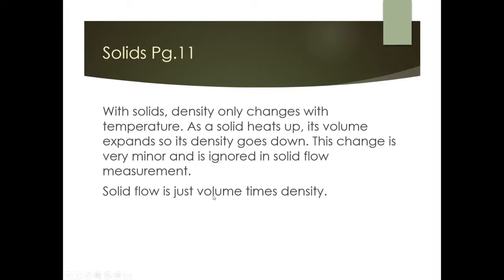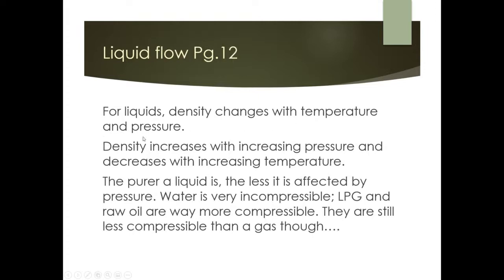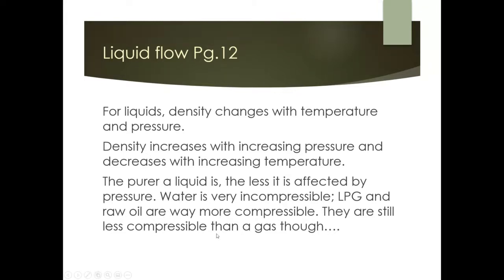For liquids, density changes with both temperature and pressure. Density increases with increasing pressure — same amount of material in a smaller space. Density decreases with increasing temperature — material expands into more space. The purer the liquid, the less it is affected by pressure. Water is fairly incompressible; liquid propane and raw oil are more compressible, but still far less so than a gas.